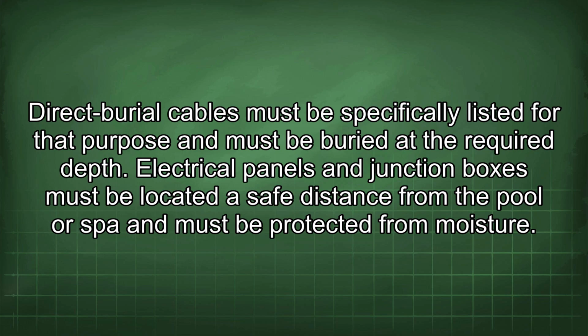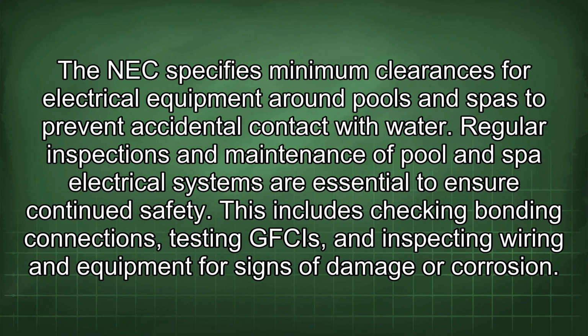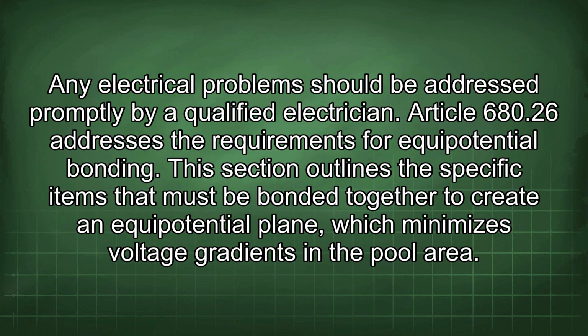The electrical panels and junction boxes must be located a safe distance from the pool or spa and must be protected from moisture. The NEC specifies minimum clearances for electrical equipment around pools and spas to prevent accidental contact with water. Regular inspections and maintenance of pool and spa electrical systems are essential to ensure continued safety. This includes checking bonding connections, testing GFCIs, and inspecting wiring and equipment for signs of damage or corrosion. Any electrical problems should be addressed promptly by a qualified electrician.